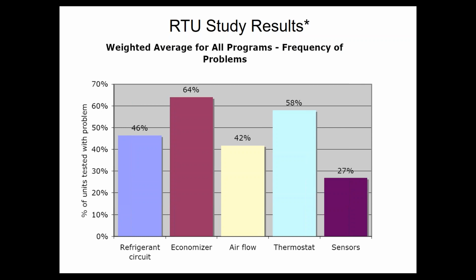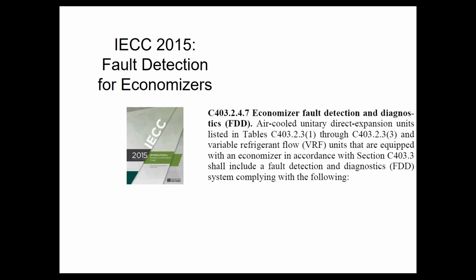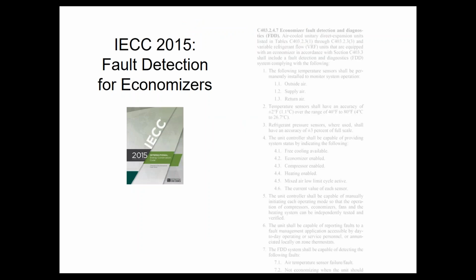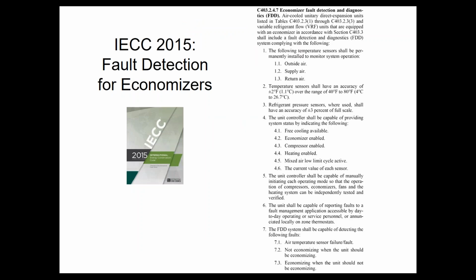Right? So because of that, some groups, such as Title 24 in California, and now ICC, on the 2015 IECC, have taken that into account. And you need a new thing called Economizer Fault Detection and Diagnostics, FDD. The whole description on what that means, I'm not going to read it to you, but essentially what that is, the economizer controller itself has to babysit and police itself for these various types of problems.